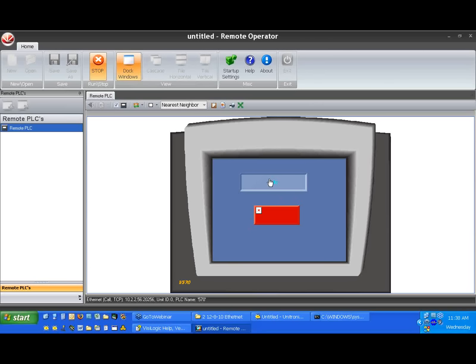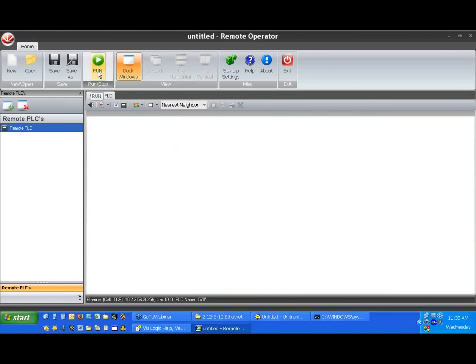Using Remote Operator, we've brought up the screen of the controller. We have our text and our image, but our image does not show up — we get a red X. Why is this? This is because we did not include a custom image file. We don't want to transfer all of the HMI variables, images, and so forth over the communication line.